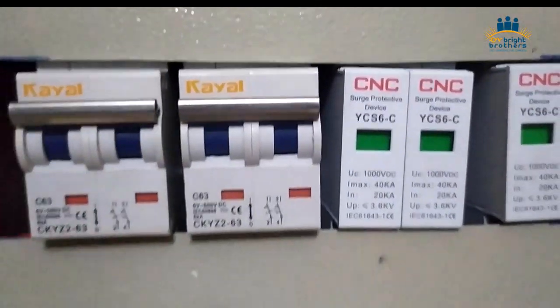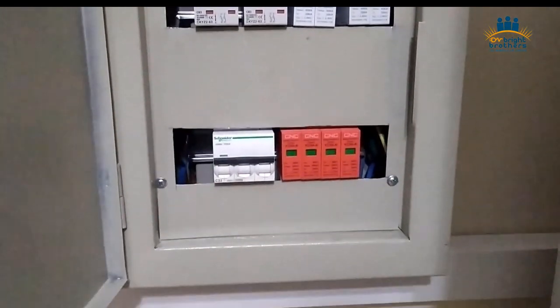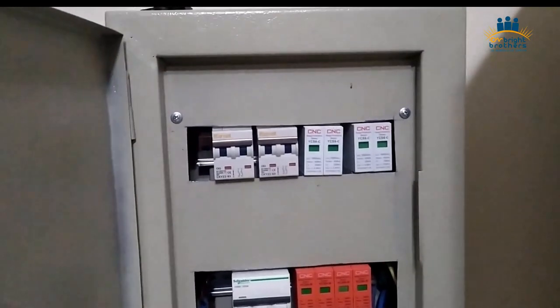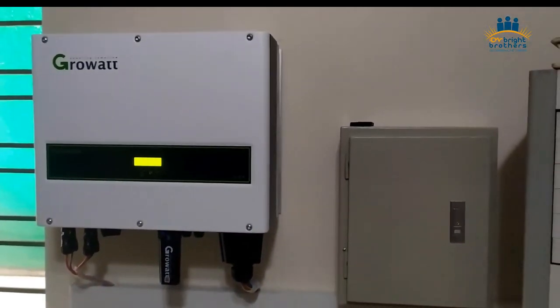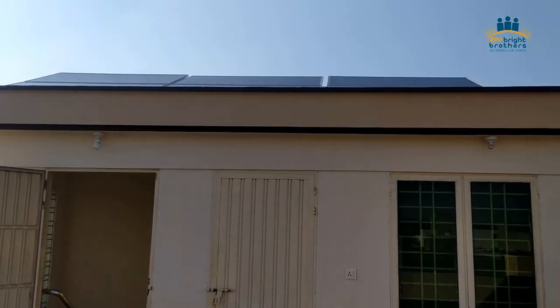We have also installed two DC SPDs with both strings, and we have also installed an AC SPD as well. These are all precautionary measures and also required by AEDB or NEPRA. You can see the installation — we tried to make it very clean.